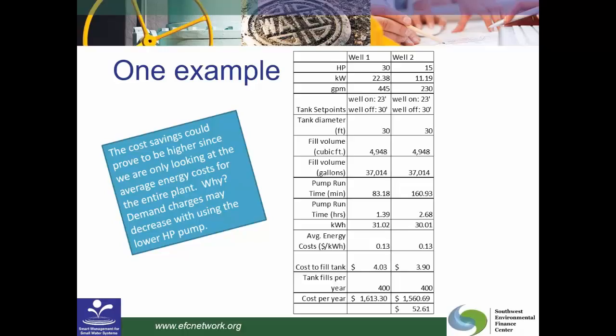So we have two wells, they're in the same well field, so the water quality is the same and the water rights are okay. We could essentially run either well to fill the tank. And we typically run well one because it's the larger pump, so it fills the tank faster. The tank set points give us 7 feet of operational room, and the tank diameter is 30 feet. So that's a total fill volume of 37,000 gallons. If we run well one, it takes us 83 minutes to fill that 7 feet. If we run well two, it takes us 160 minutes, almost double the time.